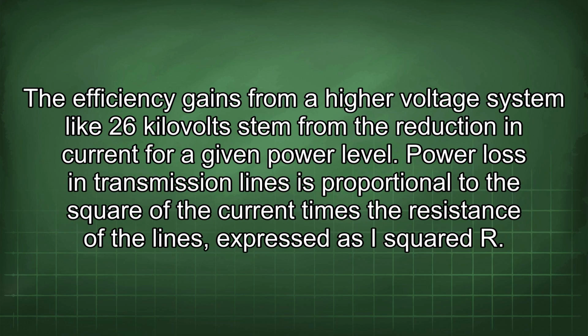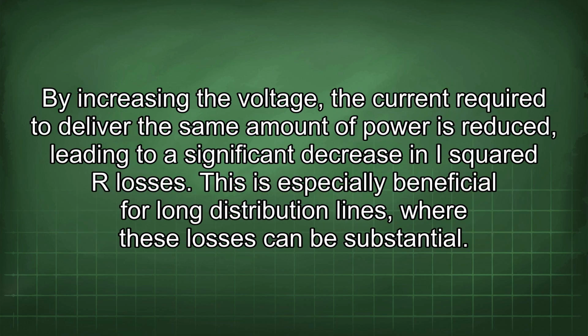The efficiency gains from a higher voltage system like 26 kilovolts stem from the reduction in current for a given power level. Power loss in transmission lines is proportional to the square of the current times the resistance of the lines, expressed as I squared R. By increasing the voltage, the current required to deliver the same amount of power is reduced, leading to a significant decrease in I squared R losses. This is especially beneficial for long distribution lines, where these losses can be substantial.